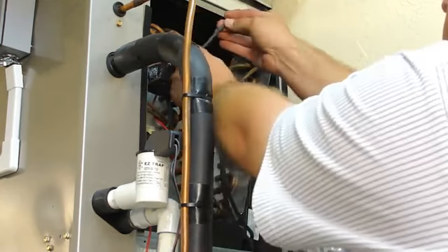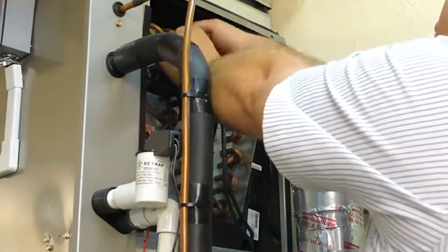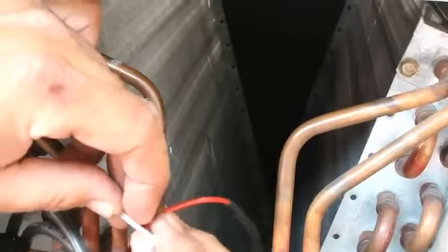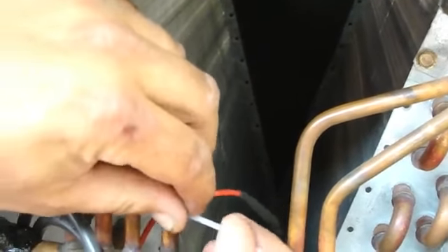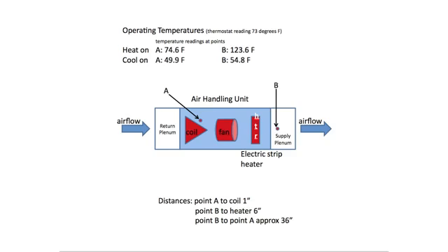Next, you'll securely attach the temperature probe wire. If needed, use the temperature cable extension, and then secure the temperature probe sensor using a zip tie. For heat pumps or straight ACs without a heating source, position the sensor near the center of the coil in an area with good airflow. For straight ACs with strip heaters, furnace, or for standalone furnace, position the sensor in the center of the supply plenum. The sensor must be down the airstream from all temperature sources. Refer to the graphic on your installation guide to help you know where the proper placement should occur.